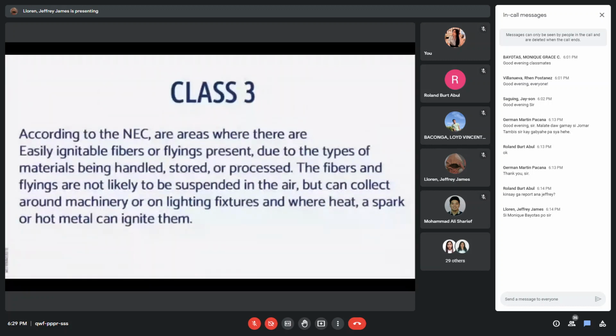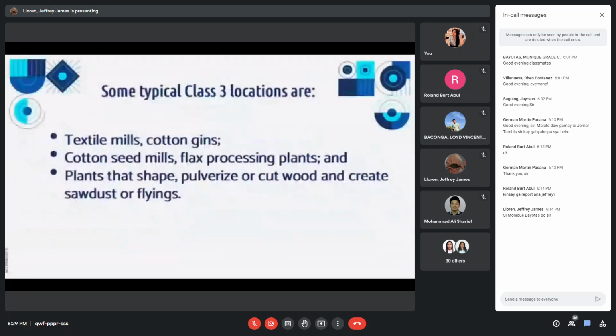So, sa class 3, according to National Electrical Code, are areas where there are easily ignitable fibers or flyings present due to the types of materials being handled, stored, or processed. The fibers and flyings are not likely to be suspended in the air, but can collect around machinery or lighting fixtures and where heat, a spark, or hot metal can ignite them. So, example, some typical class 3 locations are textile mills, cotton gins, cottonseed mills, flax processing plants, and plants that shape, pulverize, or cut wood and create sawdust or flyings.